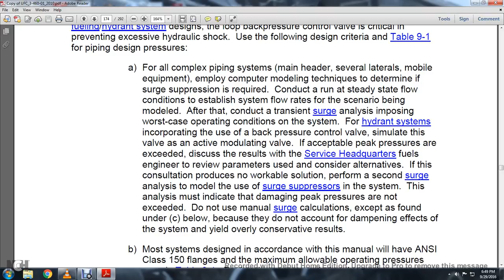Most systems designed in accordance with the manual would have ANSI class 150 flanges, with the maximum allowable operating pressure seen in Table 9.1. Design the system so that the total pressure, including the surge pressure, pump shutoff pressures, and thermal fuel expansion effects, never exceeds the maximum allowable operating pressure in any part of the system.